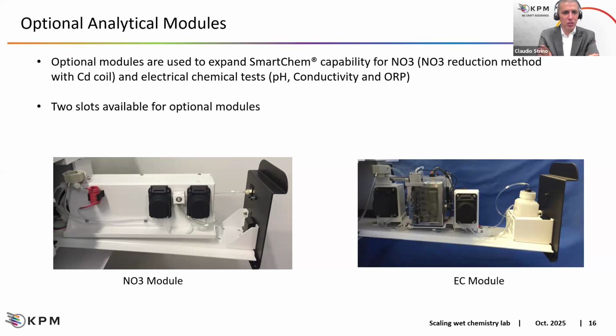The big plus concerning the NO3 module is that operators no longer need to manually handle the cadmium coil, because also the activation and regeneration procedure is totally software driven. So it means that following the driven procedure available in the software, the operators only need to load the solutions on board, and the instrument will take care of dispensing them inside the column to perform the wash and the activation.